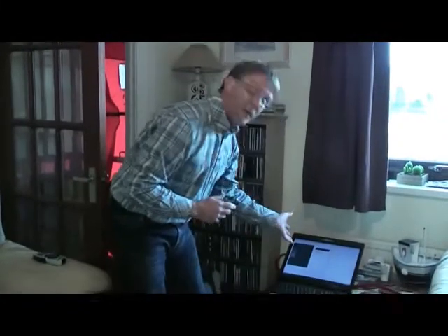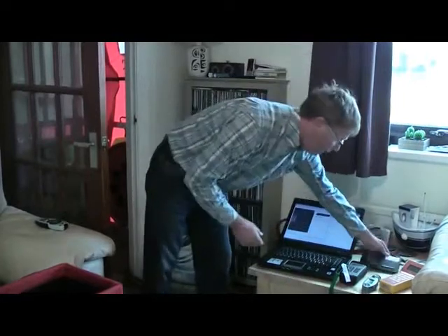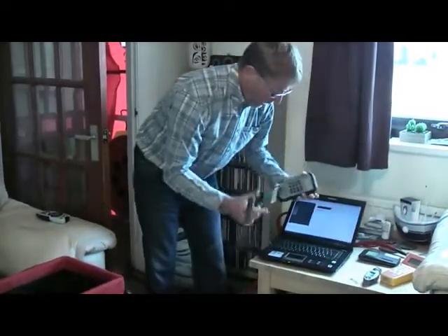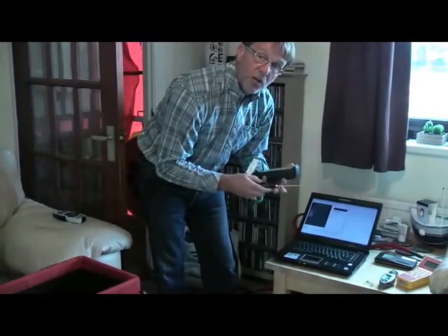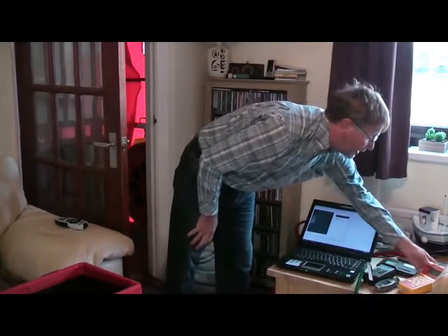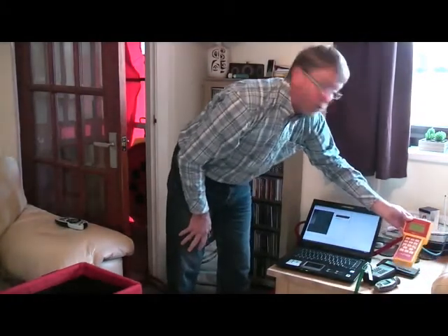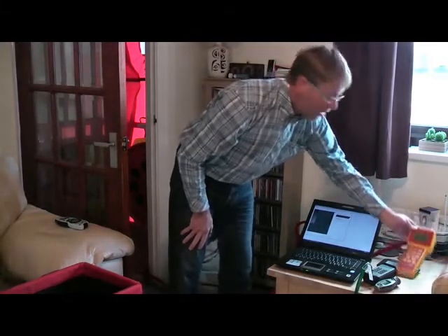These are the instruments that we'll be using today. Primarily the laptop contains the software for the air testing program, and that hopefully will give us a result on the day. We'll be measuring atmospheric pressure. We'll be measuring temperature with a very accurate instrument, both inside temperature, ground floor, first floor and external temperature. We'll also be measuring the wind speed, and this device here is, if you like, the programmer that sets the pressure for the fan.